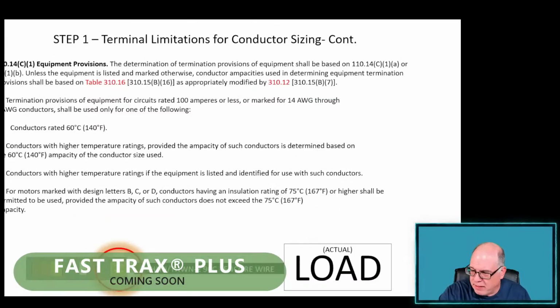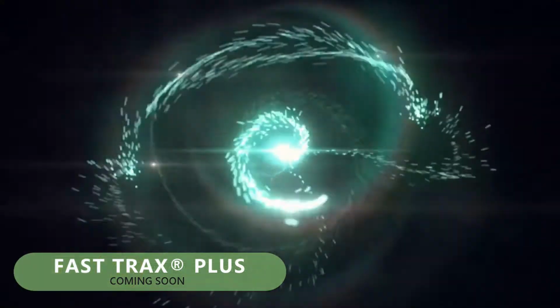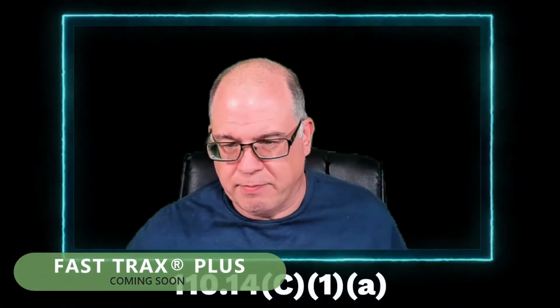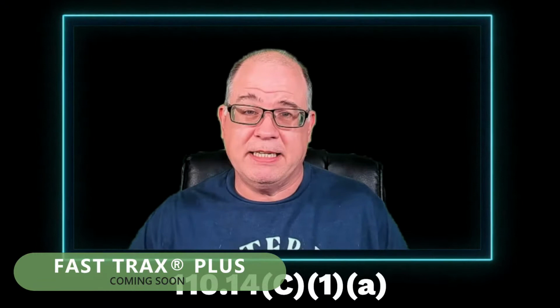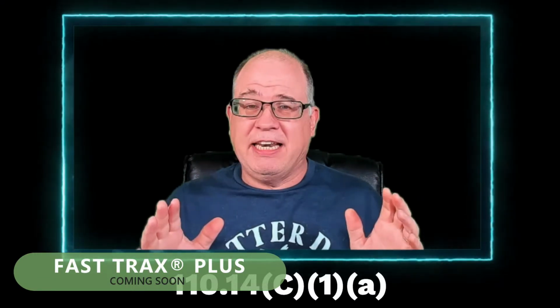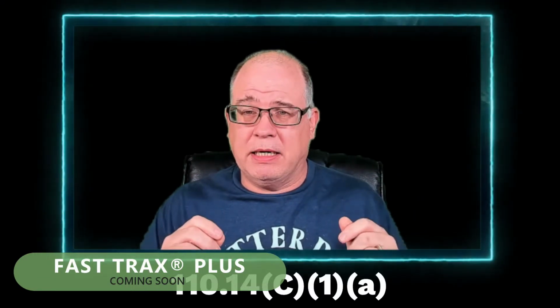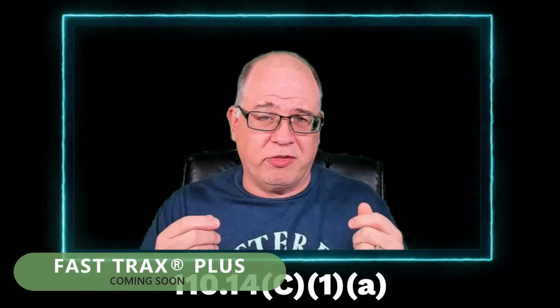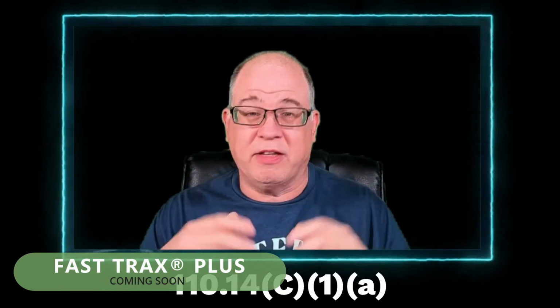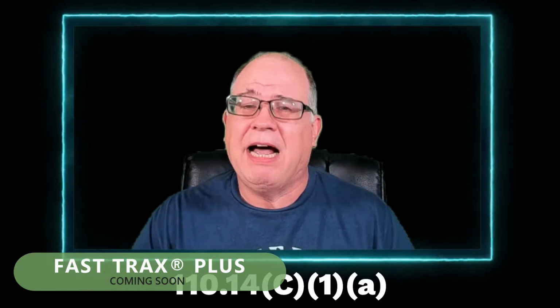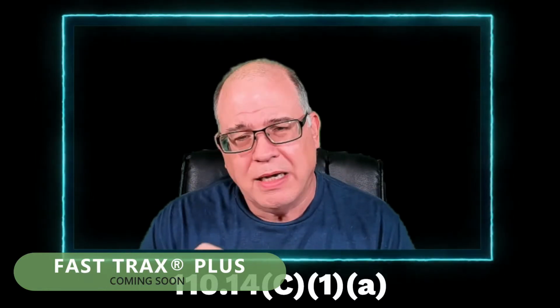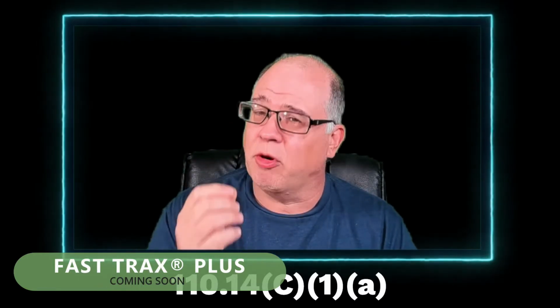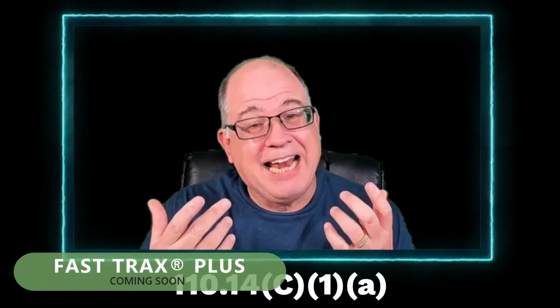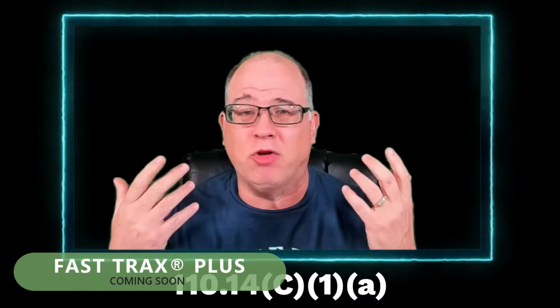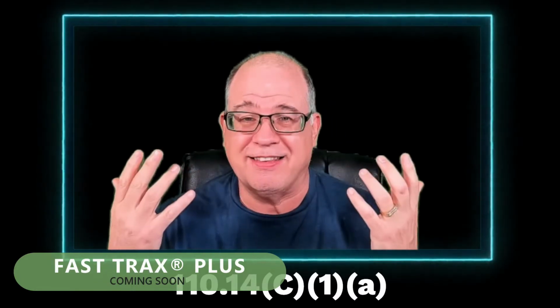All right. Just want to make sure that we're on the same page with all that as we work through this series. Now, we're obviously going to get into all the nuances in adjustment and corrections and how you do all that and the different tables in this calculation series. But I want us to start out slow. I want us to make sure we understand terminal limitations first. And now you understand that if I don't know what the terminals are rated, I'm stuck at the 60 degree column of Table 310.16. Makes sense?